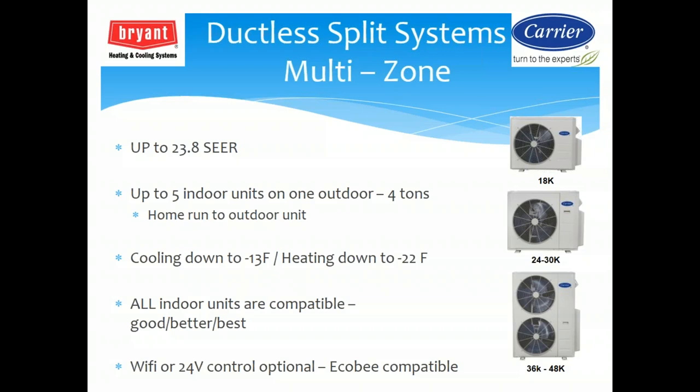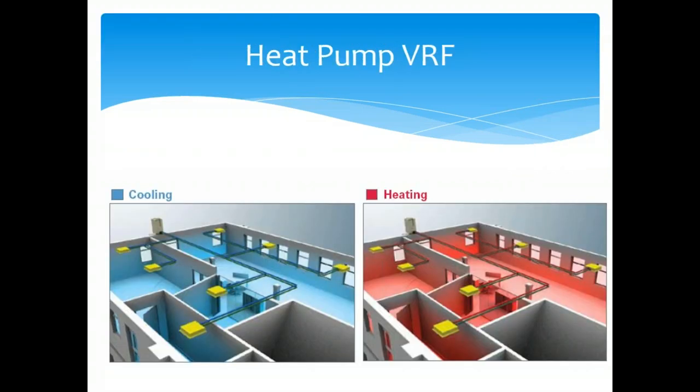Multi-zone ductless is our largest growth area — up to 23.8 SEER, up to five indoor units on one outdoor unit on four tons, cooling down to minus 13 degrees and heating down to minus 22. There's a 24-volt optional controller so we can use standard thermostats — an Ecobee, standard Carrier thermostat, or Venstar thermostat — with the system. For VRF, we do heat pump VRF for cooling or heating only, and heat recovery VRF for simultaneous heating and cooling. We use our Toshiba-Carrier VRF or Carrier VRF product.